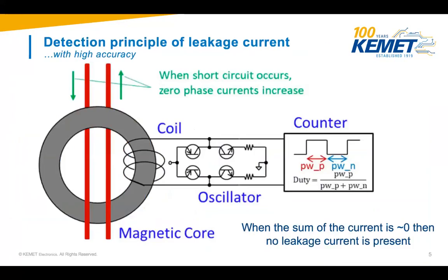So how is the detection being done? There are various possibilities to detect leakage currents, but our aim was to create a sensor which can detect AC leakage as well as DC leakage. When you have a house, flat, or apartment, you basically have an AC leakage switch or detector, usually in your switchboard. But with a DC leakage, you would probably not be aware of it, and since we're talking about high voltage, possibly coming from the car in an error case, which could be 400 volts or so, it needs to be protected so people have no possibility of being exposed to these high voltage DC levels.